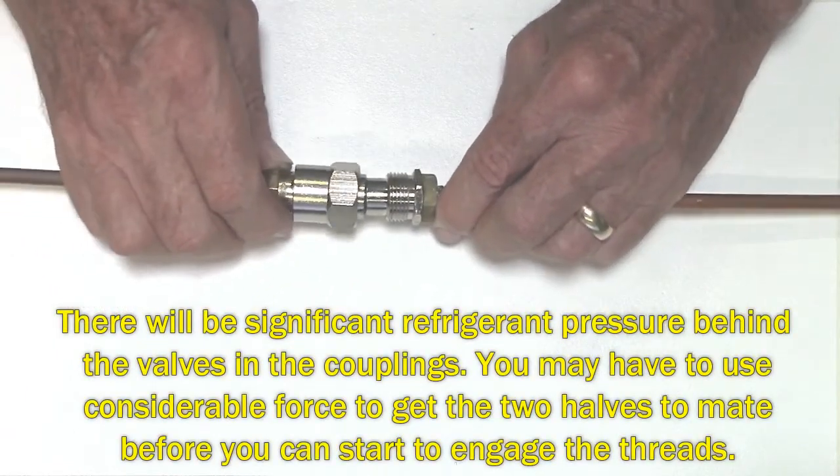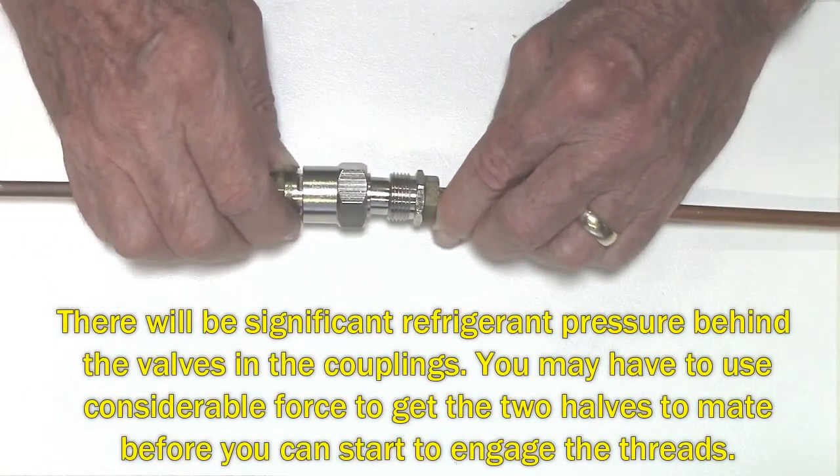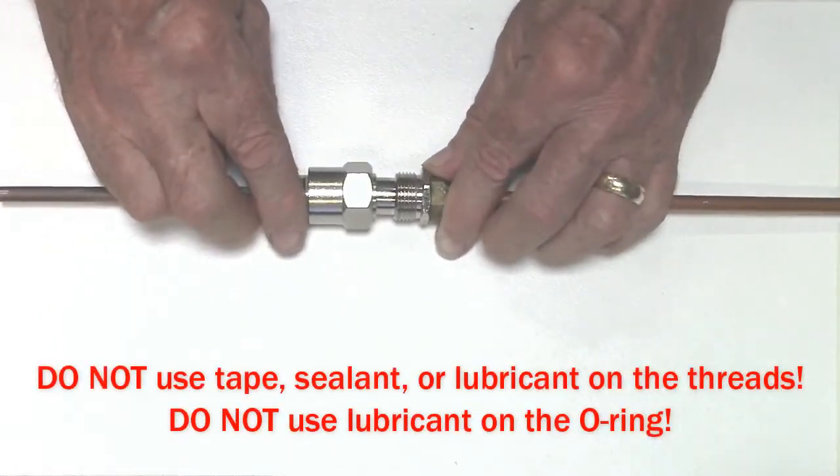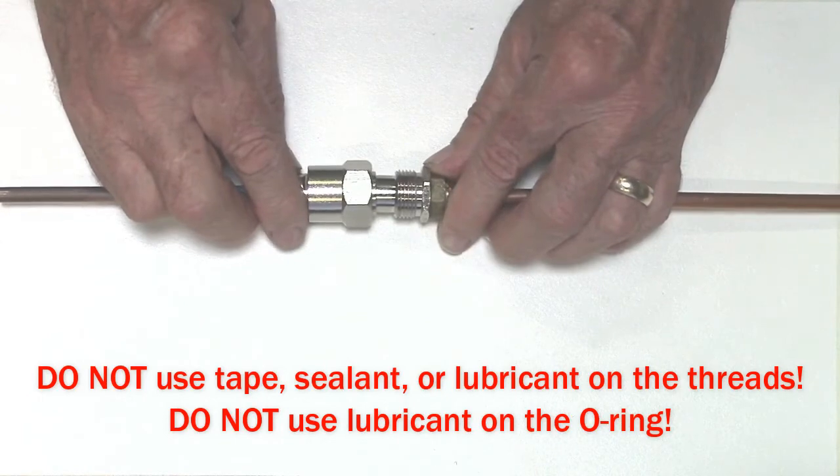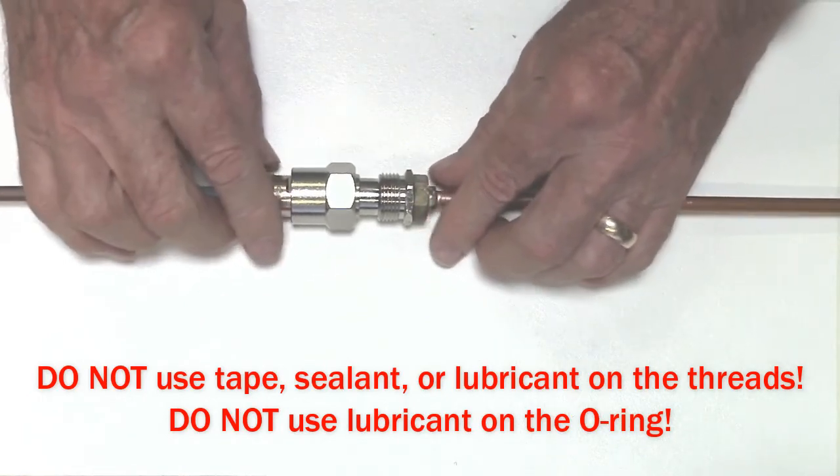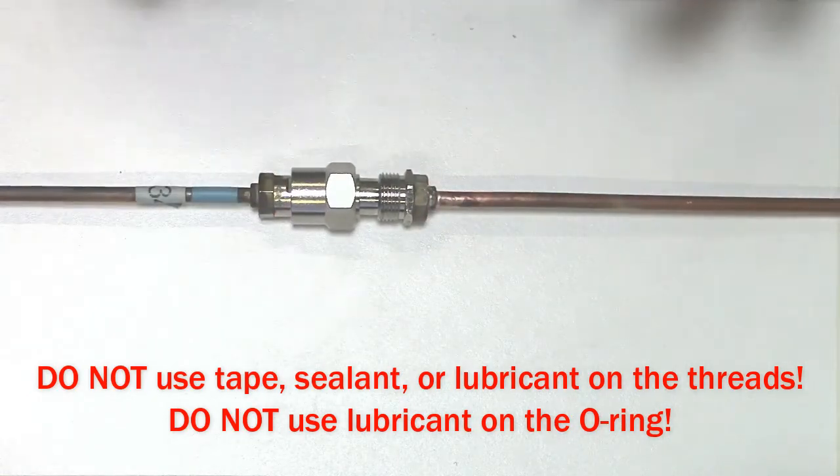Once you put it together and cover that o-ring, now the system is sealed. So don't use any liquid or tape on the threads or on the o-ring—that's not necessary. You don't need to use anything at all, just as it comes.